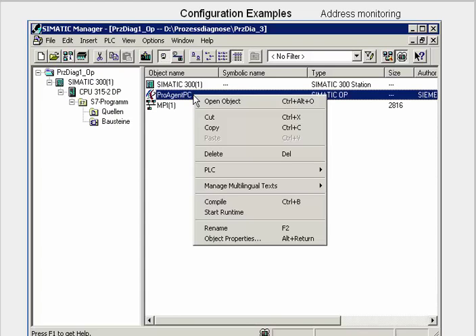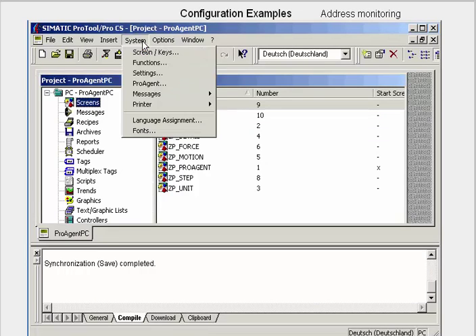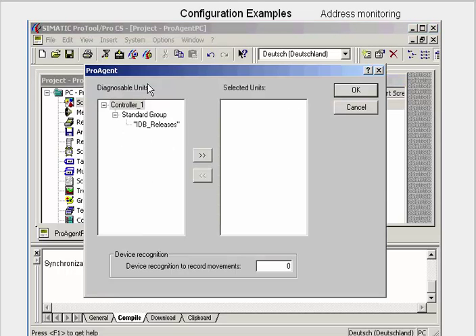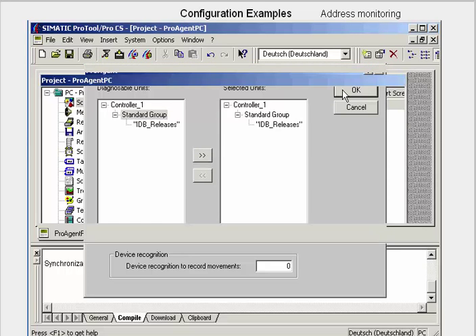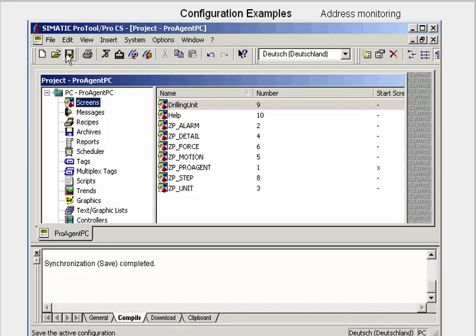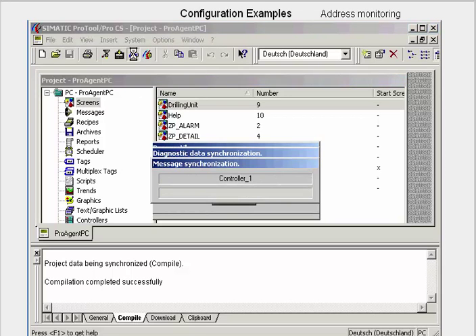We open the ProTool Pro project from the project view of the SIMATIC manager. In order to be able to configure with ProAgent, we go to the menu item System and open the dialog ProAgent. In the standard group, we select the unit that supports diagnostics and transfer it to the selected units window. We close the dialog with OK, save the project, activate generation, and then start the runtime.